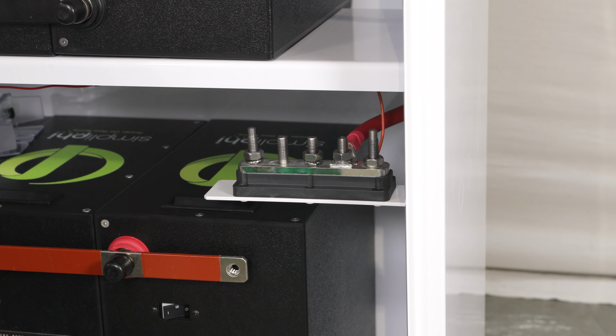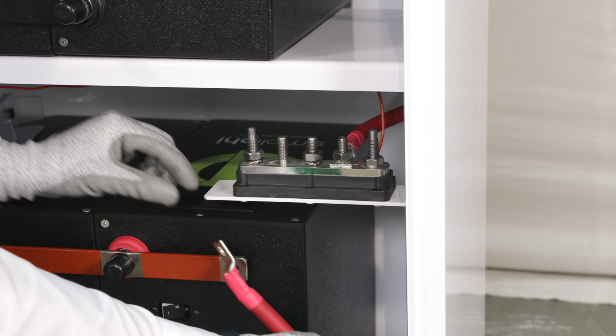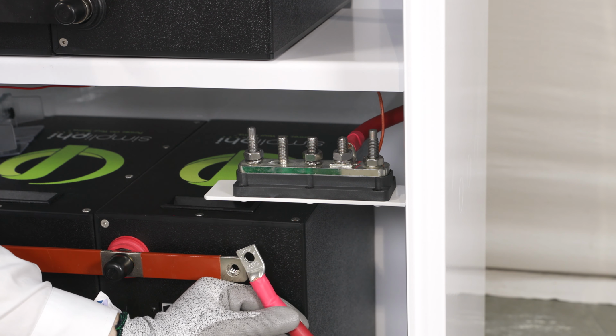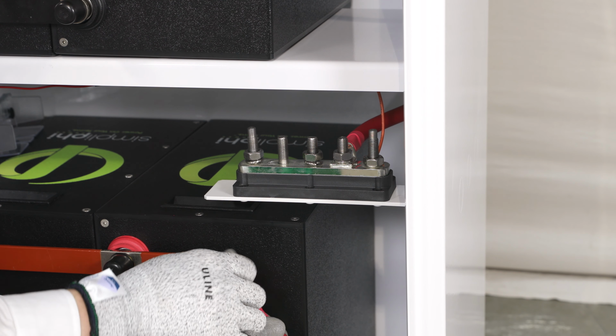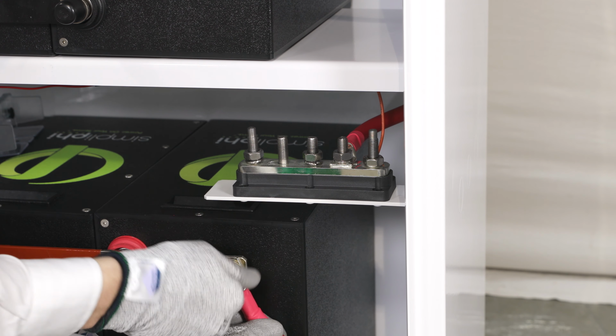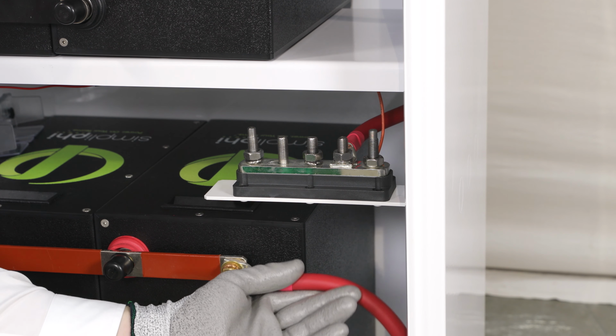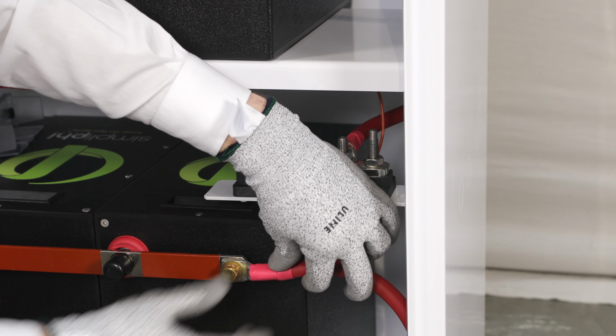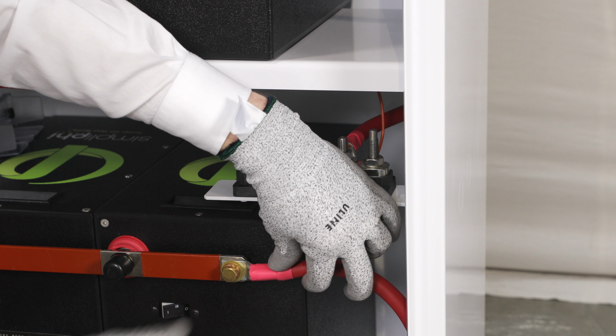Connect the 2-aught cable to the bus bar using the included 3/8-inch brass hex head cap screw. Ensure the lock washer is placed over the screw's threading first, followed by the flat brass washer. Attach the cable so that it extends 180 degrees out directly in line with the bus bar.